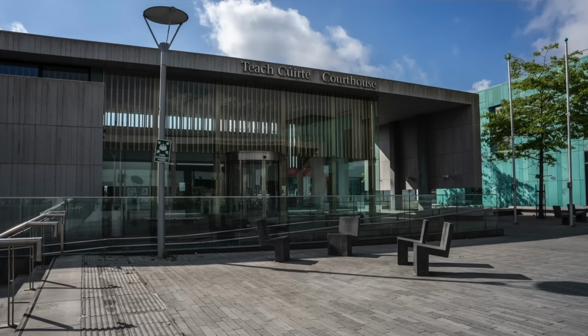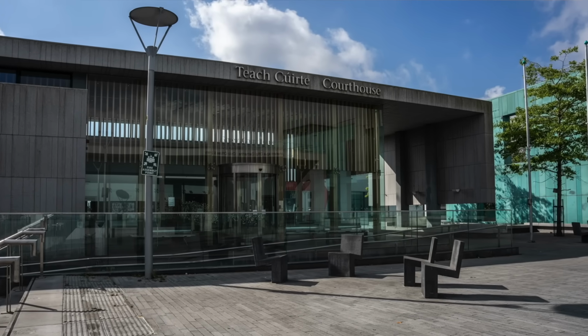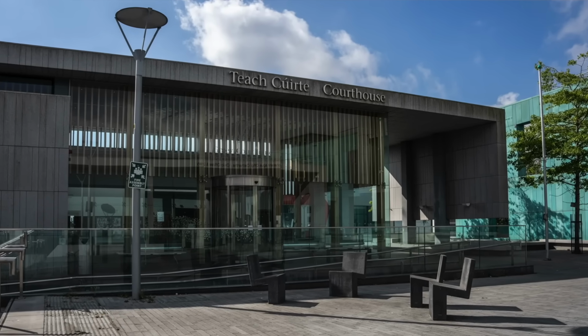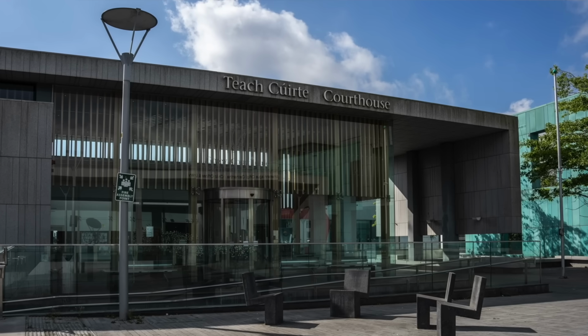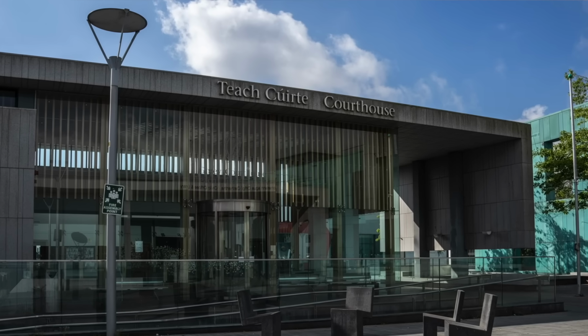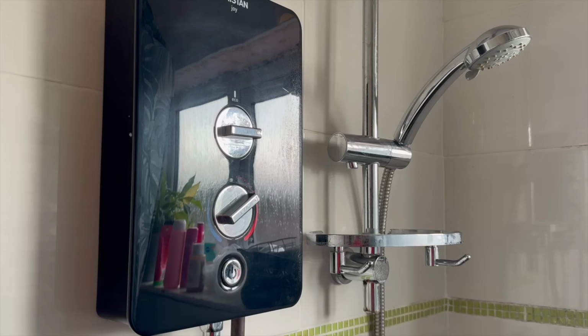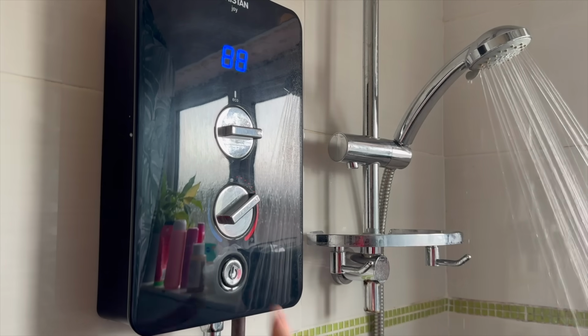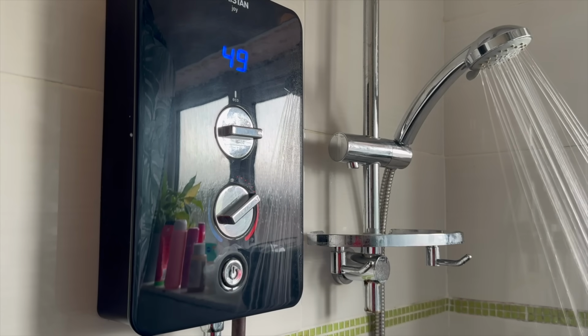Wexford District Court heard that incorrect cable sizes were used, which could have led to overheating and even a fire. Further breaches of the Irish wiring regulations included double pole isolation not being installed in a distribution board, no RCD protection on some circuits, and a new electric shower which was connected to an existing shower supply, creating a potential overload.